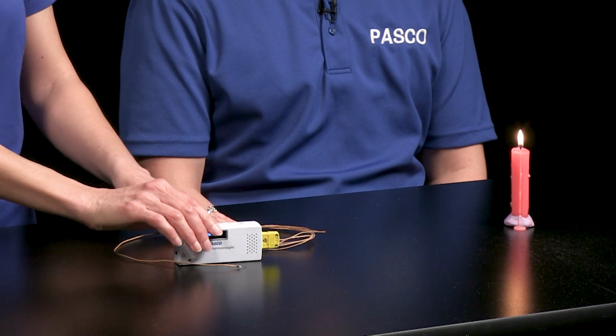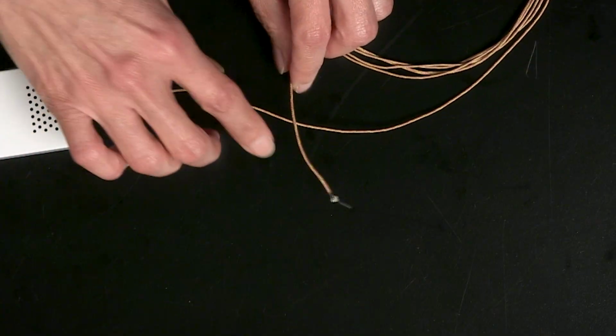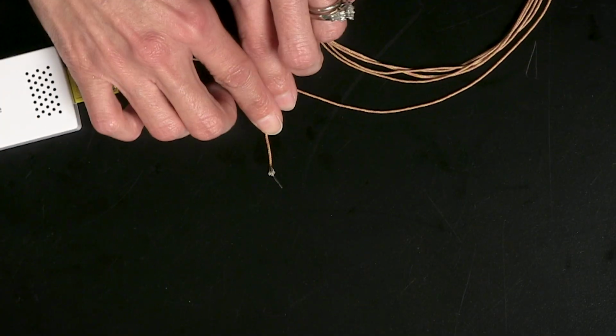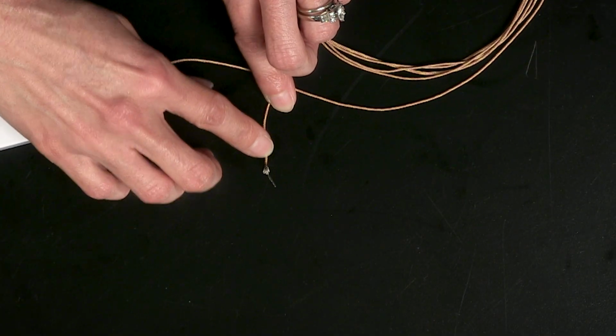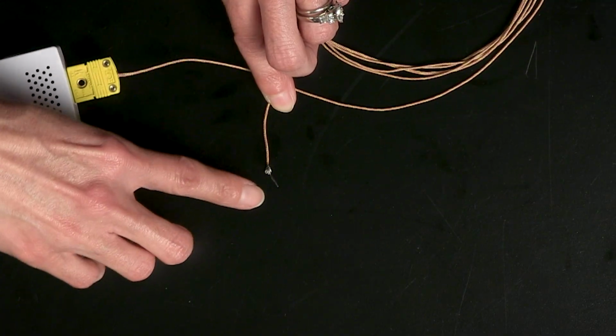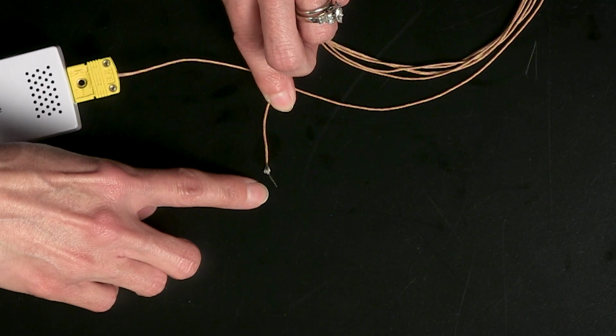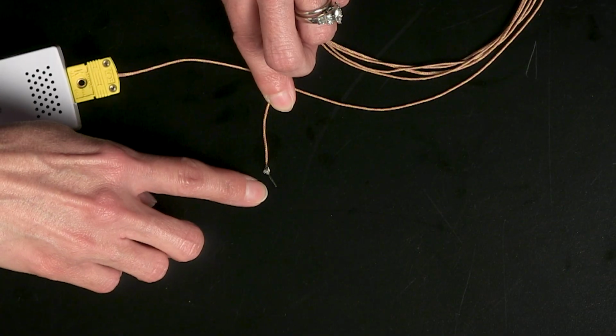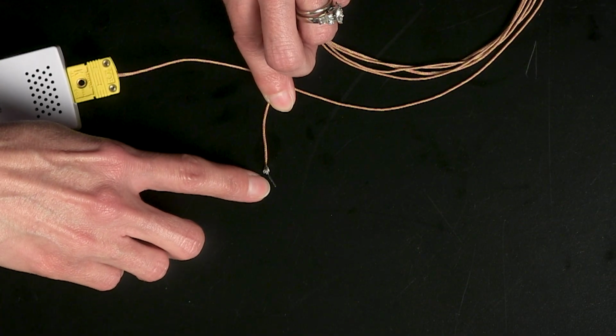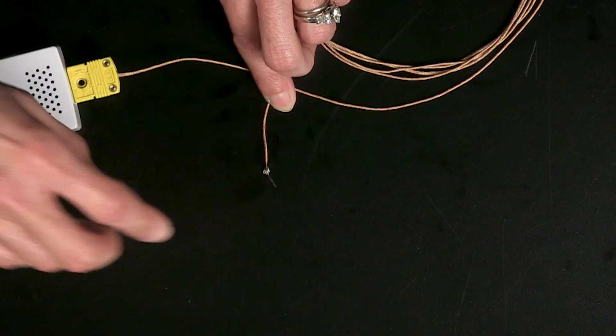probe. We will keep the insulating wrap from getting in that flame because it has a lower heat tolerance than the sensing part of the probe, which is these last couple of millimeters at the end of the probe where the two wires are welded together. Now I'll start recording data.